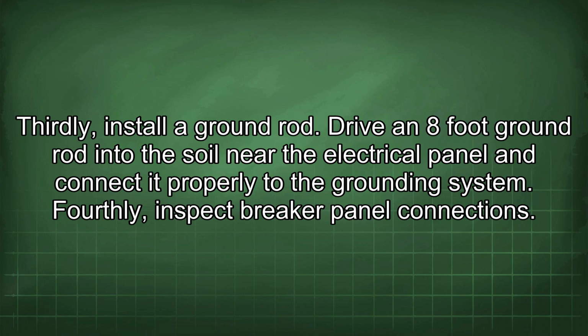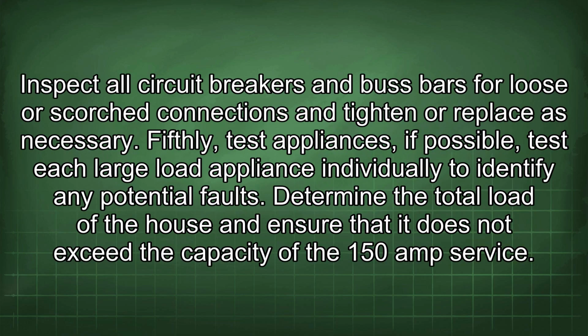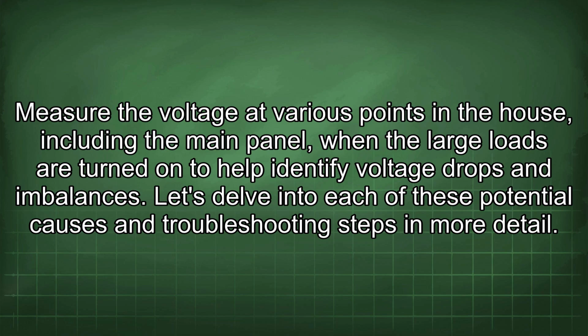Fourthly, inspect breaker panel connections. Inspect all circuit breakers and bus bars for loose or scorched connections and tighten or replace as necessary. Fifthly, test appliances. If possible, test each large load appliance individually to identify any potential faults. Determine the total load of the house and ensure that it does not exceed the capacity of the 150 amp service. Measure the voltage at various points in the house, including the main panel, when the large loads are turned on to help identify voltage drops and imbalances.